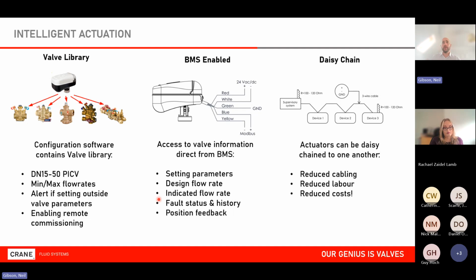And as I'll show you in a moment, we can now gather even more information with versions which have temperature sensors connected to them as well. So now we can generate information such as flow temperature, return temperature, delta T. Now that I have flow rate and delta T, I can generate power. So effectively, I can use these as a form of heat meter. And all of that reduces the amount of components, complication, and setup within our system.